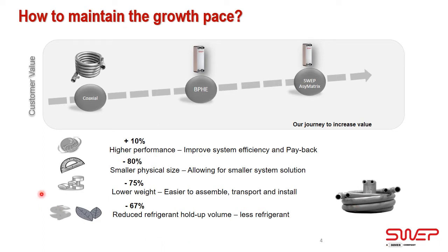Well, going from the most commonly used heat exchanger technology today, the coaxial heat exchanger, to the brazed plate heat exchanger, and even more so the asymmetric brazed plate heat exchanger, will allow the heat pump system to become high performing with a higher EER and COP, at least 10% better. The heat exchanger has a smaller physical size, allowing for a smaller system solution, making it easier to assemble, to transport, to get installed into the final location. Less weight, again, easier to assemble, transport and install. And a drastically reduced refrigerant holdup volume, leading to less refrigerant, less GWP, and also less cost for refrigerant.